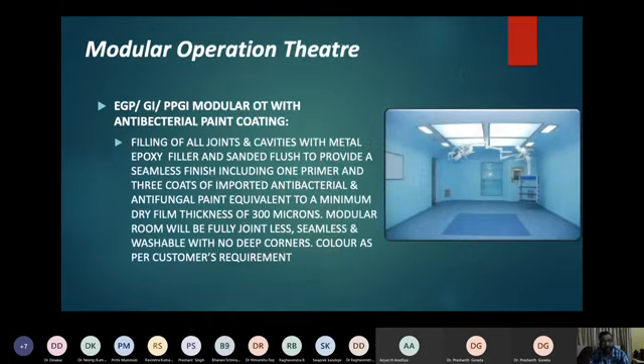The next option is antibacterial paint coating, which gives long-lasting protection for the modular OT up to 15 to 20 years, as cleaning is very easy. It has a dry film thickness of 300 microns. Some people apply this painting after puff paneling, but in some places doctors prefer to do the painting on stainless steel as well.